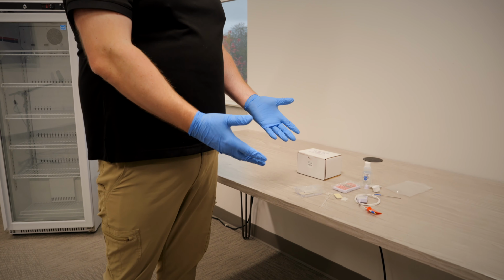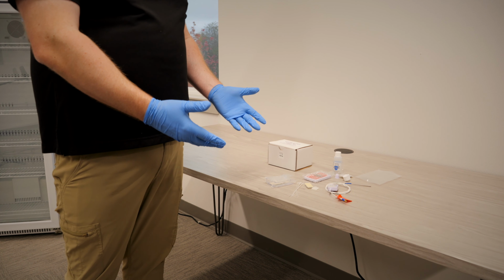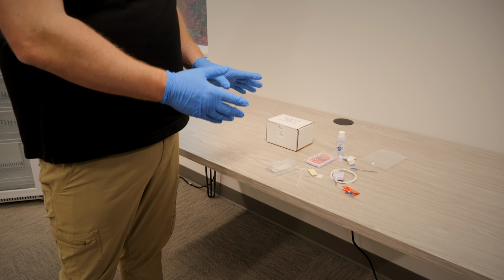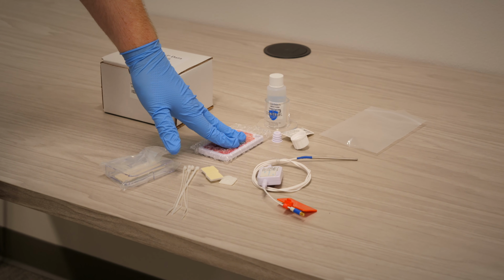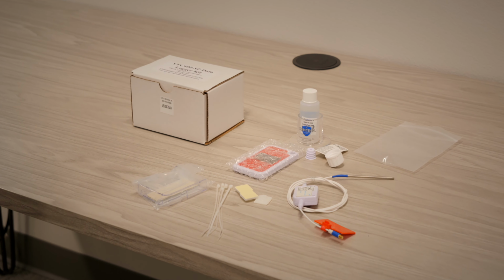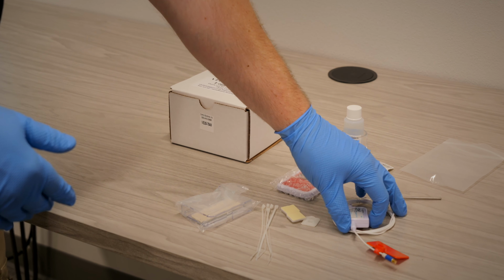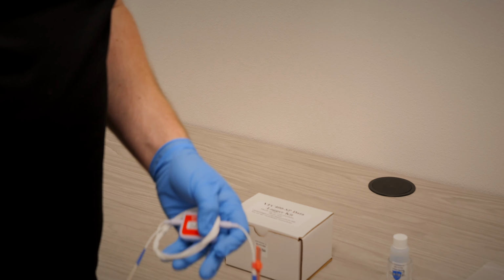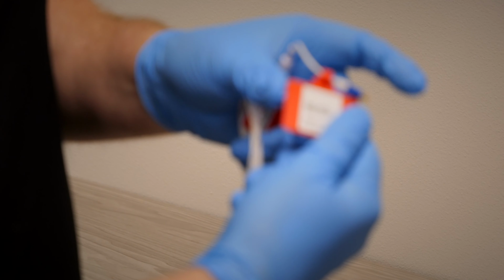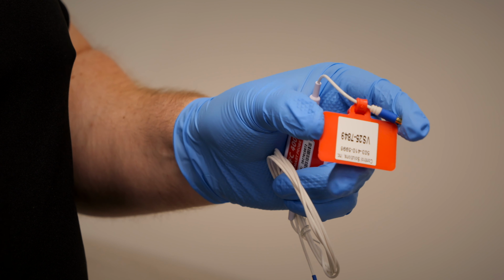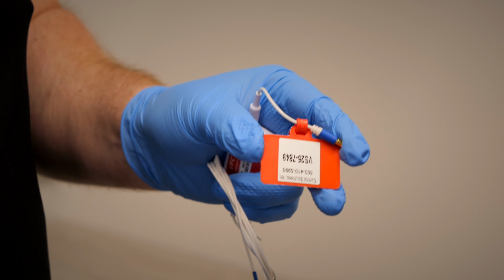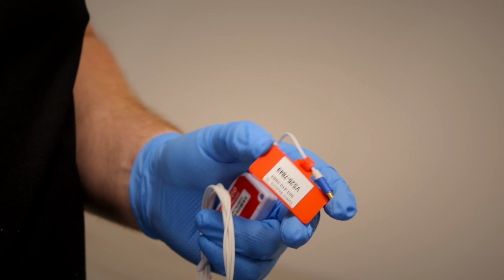So here on our table is all the installation accessories that we'll need to install it. Now, for those with keen eyes, you may notice you do need a calibration certificate. For the purpose of this video, one is not included here, but your package will have a calibration certificate related to just your specific smart probe cable. The calibration sticker will be found on this red tag that will reflect the date it was calibrated on and the date it expires.